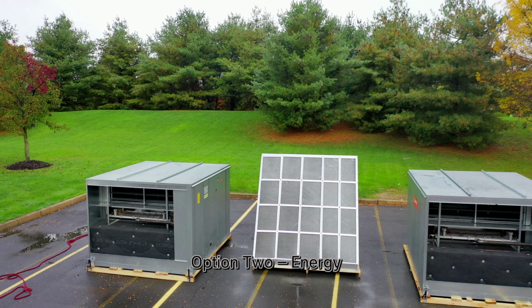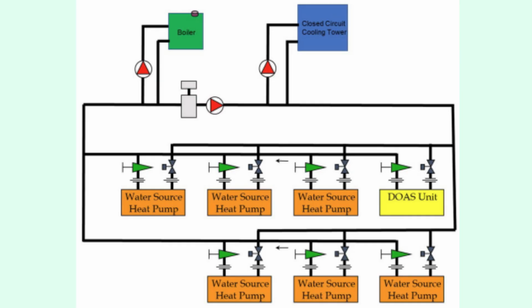Option 2. Energy Recovery Unit, or ERU. An ERU transfers both heat and moisture between the exhaust air and the incoming outdoor air using a desiccant wheel or similar media. It's an excellent way to reduce operating costs and is often used alongside a DOAS for added efficiency. However, by itself, an ERU usually cannot manage the full latent load on hot, humid days. It also requires routine maintenance. The wheel, filters, and motors must stay clean and balanced to maintain performance.